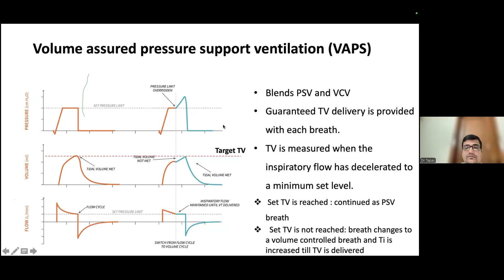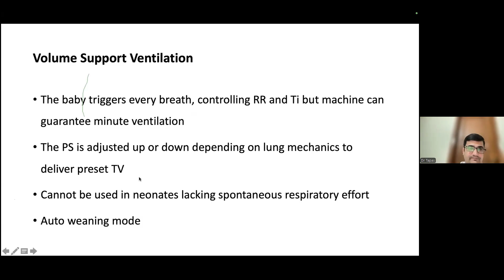So next, coming to volume support ventilation, again it's a mode of volume targeted ventilation which works in babies who are spontaneously breathing. Here the baby will have complete control over the rate and the TI, but the machine will guarantee the minute ventilation. How will it guarantee the minute ventilation? It will do so by adjusting the pressure support either up or down depending on the lung compliance to deliver the preset tidal volume. So again, it's an auto-weaning mode of ventilation, and it should not be used in babies who lack spontaneous respiratory effort. So next, coming to the NAVA.